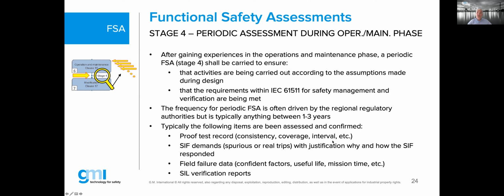Also, the interval. Many people say, oh, with us, we do an interval of 3 years, and then the actual time is 3 years plus so many months, because you may not have time when a 3 years timer was about to be there. That's why with some end users, it's going to be very critical, and it's going to give you a window of 6 months before the target date is due. They will ask you to start to plan the test and to carry it out.